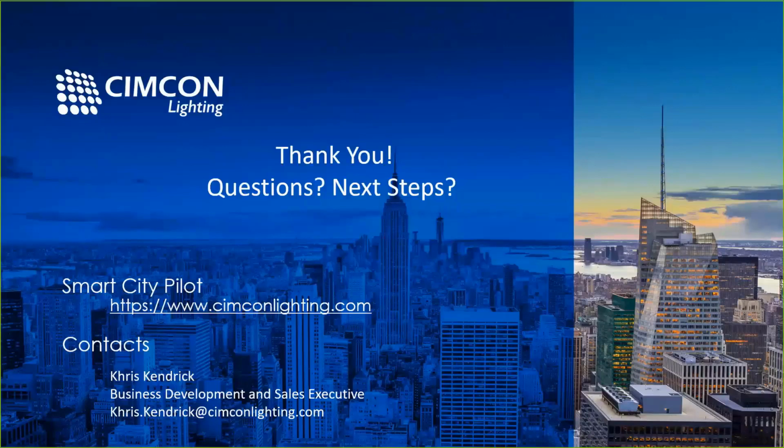We automate that process by, as soon as the luminaire has a SLC attached to it, it starts to beacon back to the LG software through our gateway, and we automate the process by commissioning that SLC onto our back-end software. So it's a very automated process. It can happen in the field, or it can happen back at the central office.